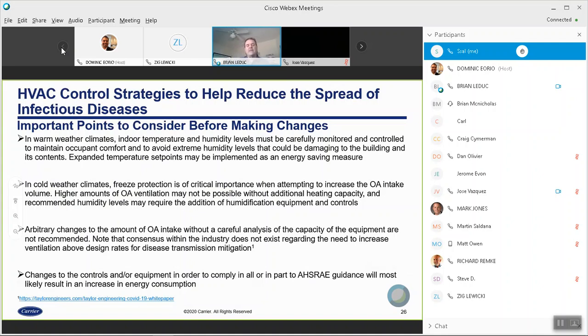One thing we don't recommend is making arbitrary changes to the amount of outside air intake without really doing a careful analysis of the capacity of the equipment. The customer might say, well, can you increase it by 20% above my design minimum, or 30% or 40%? I would not implement a change like that unless you understand the true capacity of the equipment as to whether or not it can tolerate that kind of an increase. Again, middle of summer on a design day, middle of winter on a design day, you have to be really careful in terms of increasing the ventilation. And again, there will be applications where it's just not possible.